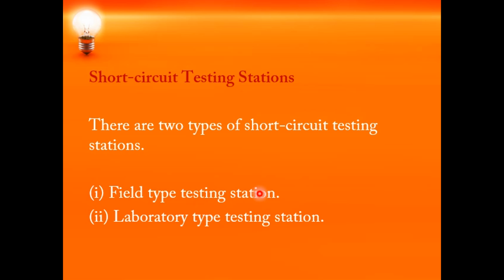And say in real time, if the load is getting varied, then the power which is available for testing the circuit breaker will be entirely varying. That also will be a problem. And you cannot control the transient voltage or the recovery voltage. That is the drawback of this particular field type testing station.